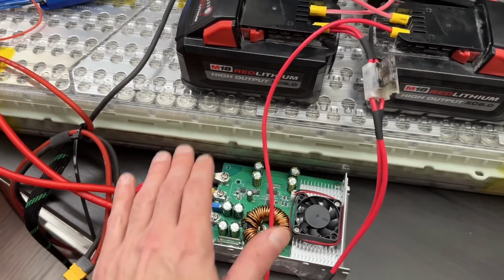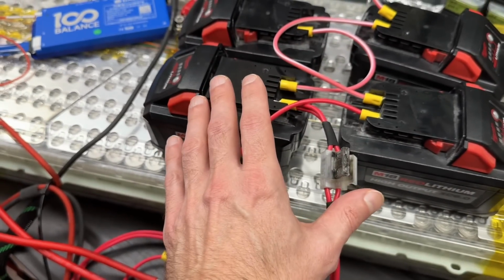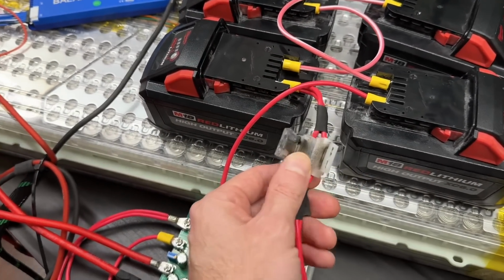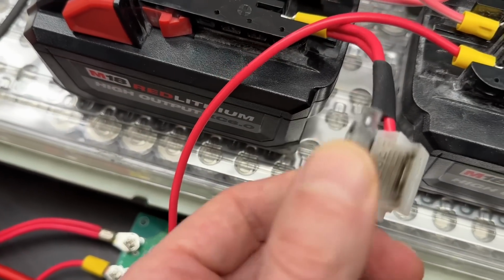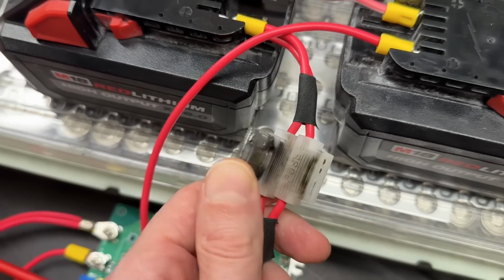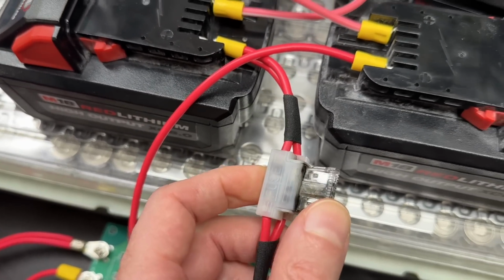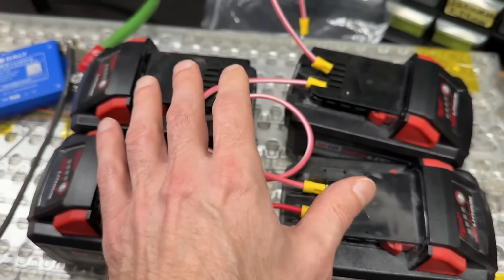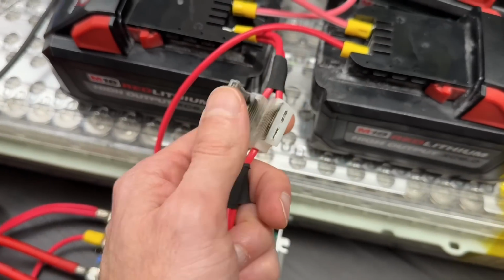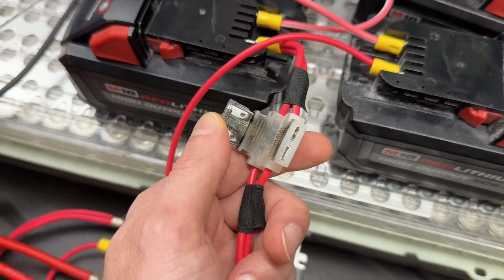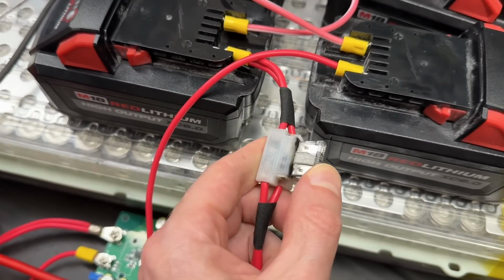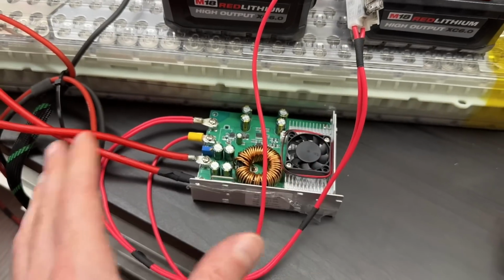We did put too much load on this fuse, which is clearly popped, and this is where the flash came from. There's quite the arc that would have been created here, considering the amount of voltage we have. That's why we always want to make sure we put the appropriate fuse in here, because without this fuse, we would have made a really big mess.